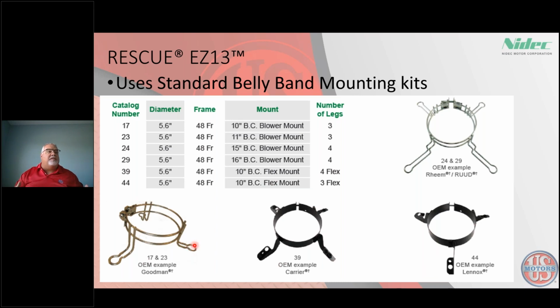I know there are other options out there for you. This is just to show you, yes, we're using the standard belly band kits. And I would suggest making sure that we have that kit, because not all of these motors have a kit on them. Some of them have welded feet or welded legs, so we're definitely going to need a kit when we replace these motors. And you'll know that when you're out in the field.